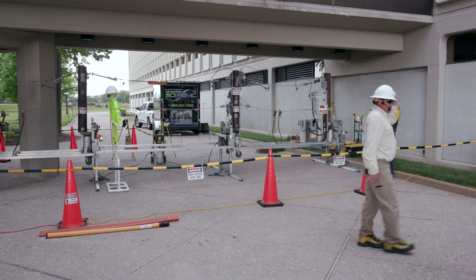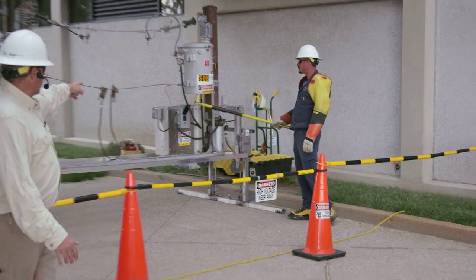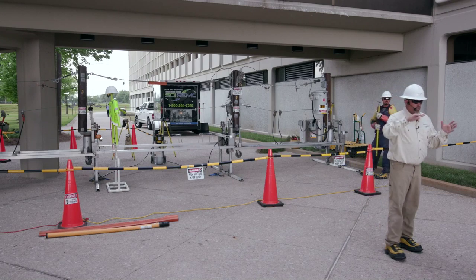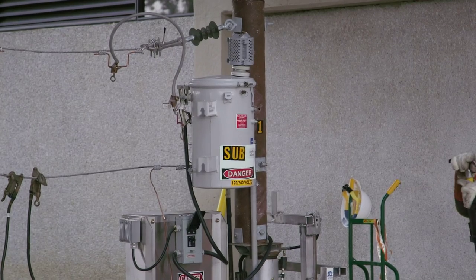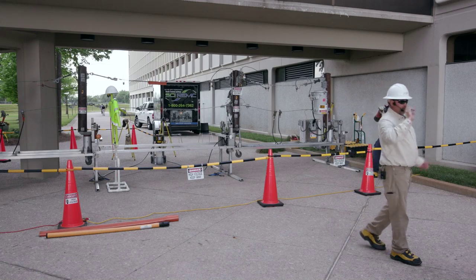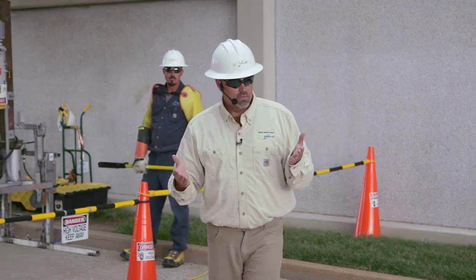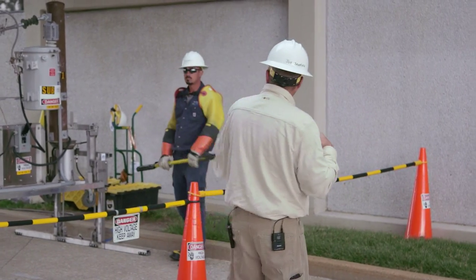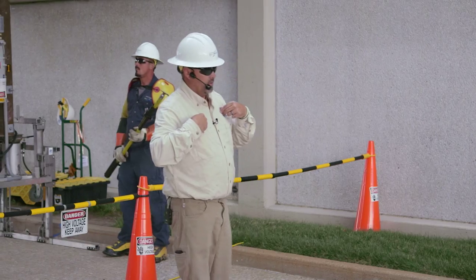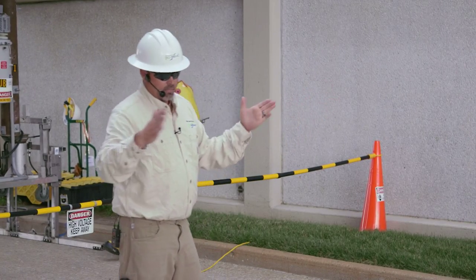You can hear the generator in the background — that's our generating plant for our purposes today. We're coming out of that generator to this transformer. The transformer does one of two things: it comes in at 7,200 volts and comes out at 120/240. But if you put 120/240 back through it, it gives you 7,200 volts out the top. That's what we're doing today — back-feeding it. What could happen is if a storm hits and a consumer hooks up their generator wrong, it could energize back onto our line. So we put grounds on each side of us to protect us — it would protect us but probably burn up their generator.